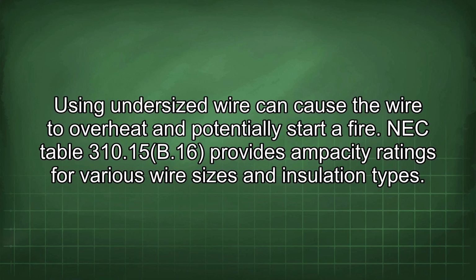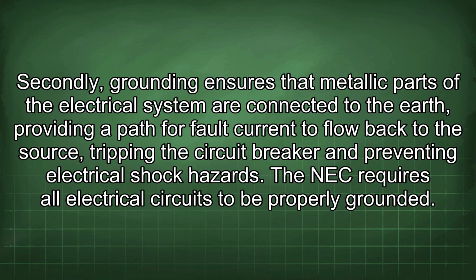NEC Table 310.15(B)(16) provides ampacity ratings for various wire sizes and insulation types. Secondly, grounding ensures that metallic parts of the electrical system are connected to the earth, providing a path for fault current to flow back to the source, tripping the circuit breaker and preventing electrical shock hazards. The NEC requires all electrical circuits to be properly grounded.